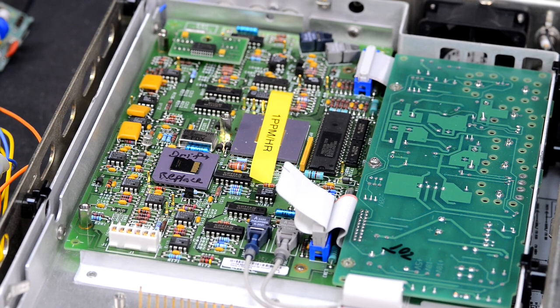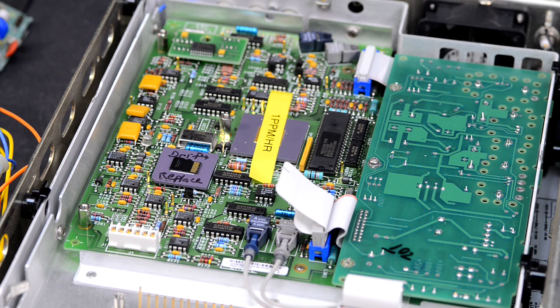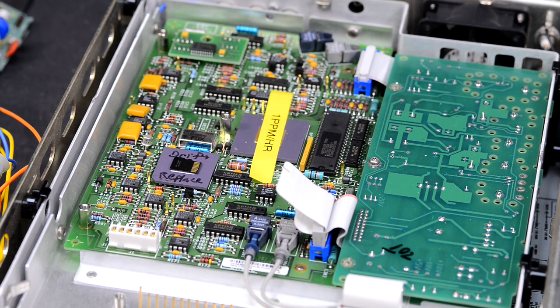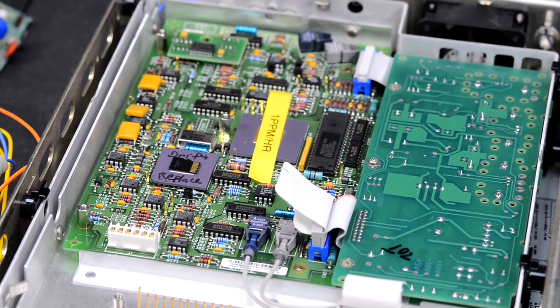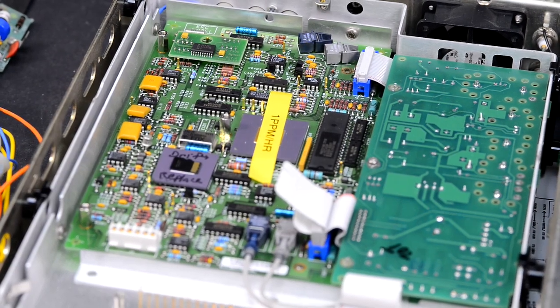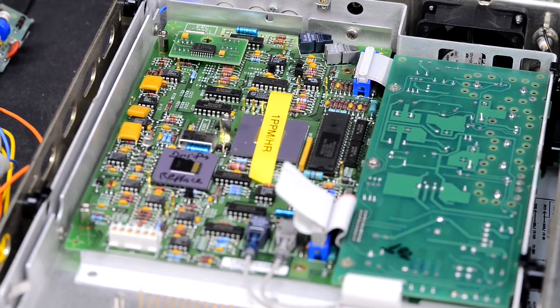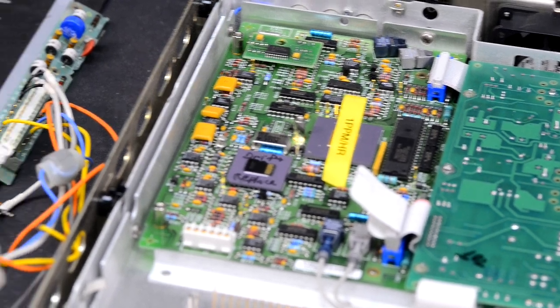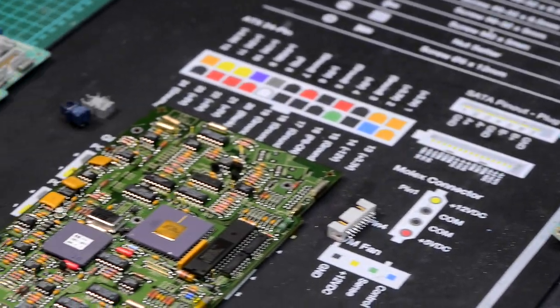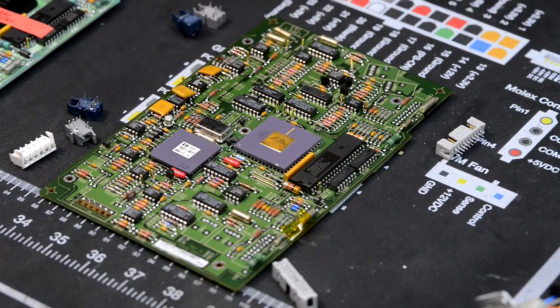Sadly, manufacturers today don't support component repairs anymore, so typically a faulty A3 means a complete board replacement, and that costs multiple thousands of dollars. Maybe in the future we will win more rights for repairs, but for now it's not cheap to fix instruments like this 3458A. The currently installed board drifts by about 1 ppm per hour, so we will try a different board instead that is sitting on my bench.